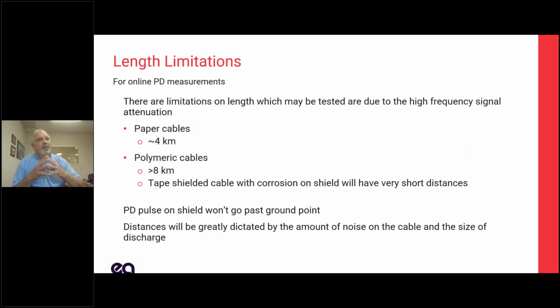Questions come up a lot: how long a cable can I test? Well, how clean is your cable? How much noise is there? And how big is your PD source? Those two are going to affect it. So we can't definitively say that you can test a 5-kilometer cable and not a 6-kilometer cable.